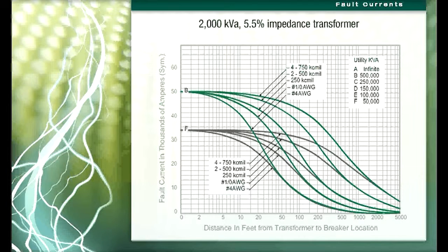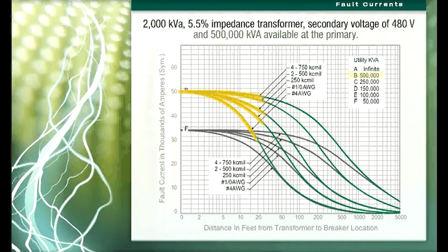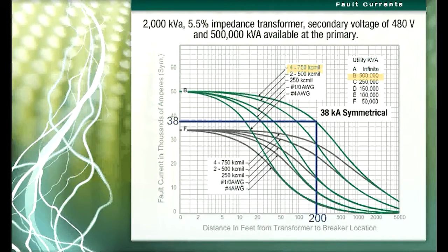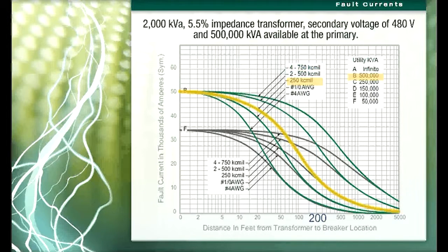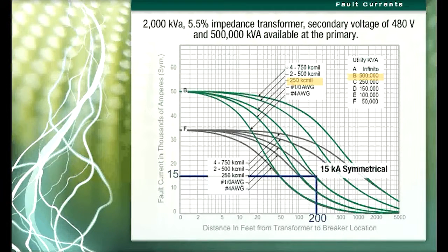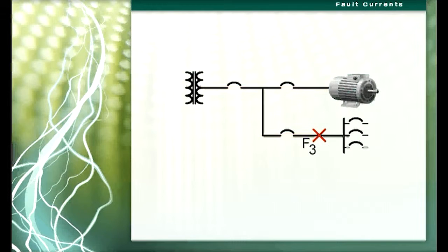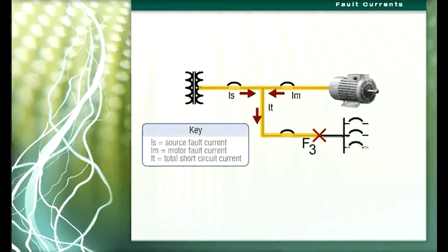Given a 2000 KVA, 5.5% impedance transformer, secondary voltage of 480 volts, and 500,000 KVA available at the primary of the transformer, fault current at 200 circuit feet for four 750 kcmil per phase conductors is approximately 38 kA symmetrical. If the conductors are one 250 kcmil per phase, the fault current at 200 circuit feet is approximately 15 kA. Total short circuit current at a fault is the sum of that available from the source and the current contributed by the load. The load contribution comes from running motors, as the motors become generators.